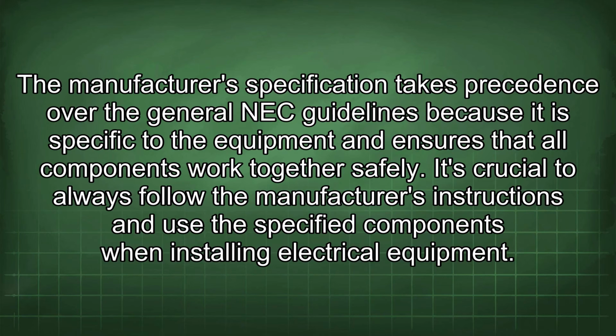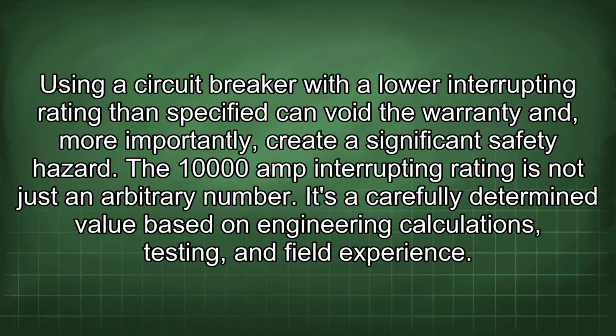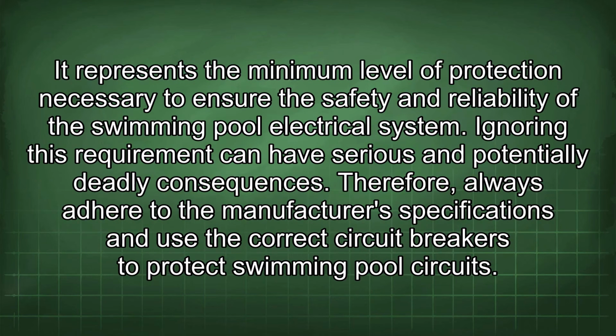It's crucial to always follow the manufacturer's instructions and use the specified components when installing electrical equipment. Using a circuit breaker with a lower interrupting rating than specified can void the warranty and, more importantly, create a significant safety hazard. The 10,000 amp interrupting rating is not just an arbitrary number. It's a carefully determined value based on engineering calculations, testing, and field experience. It represents the minimum level of protection necessary to ensure the safety and reliability of the swimming pool electrical system.